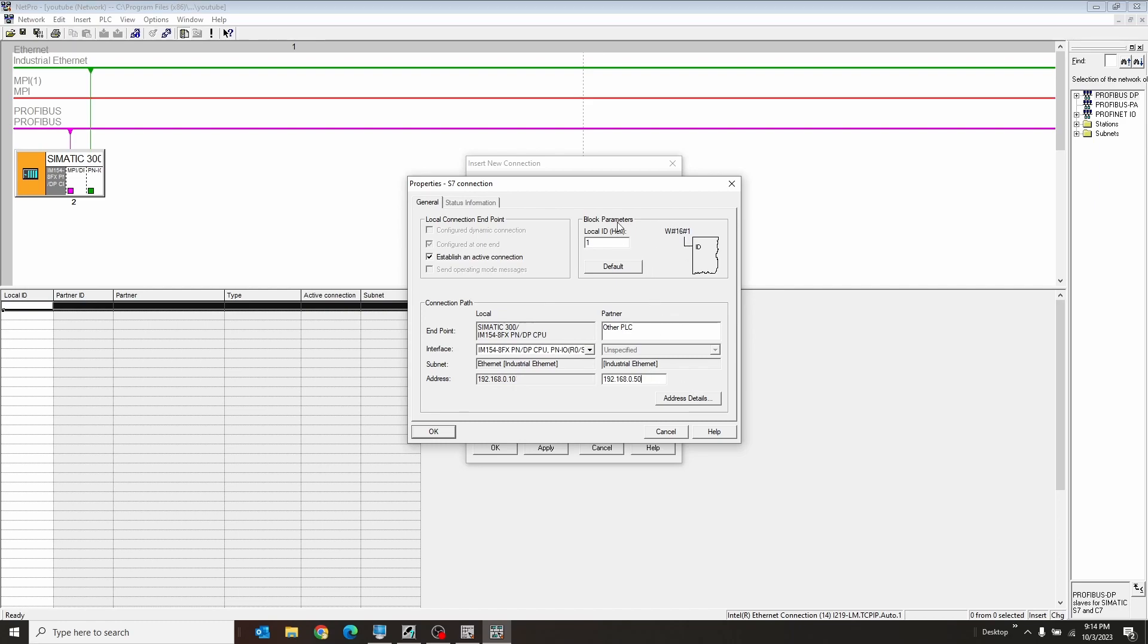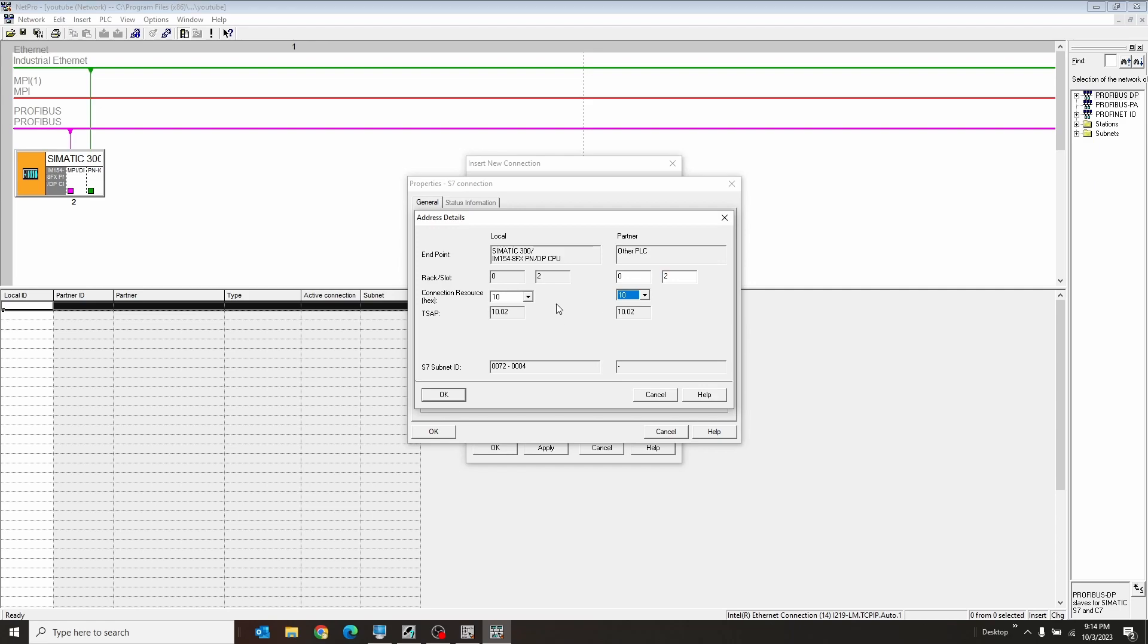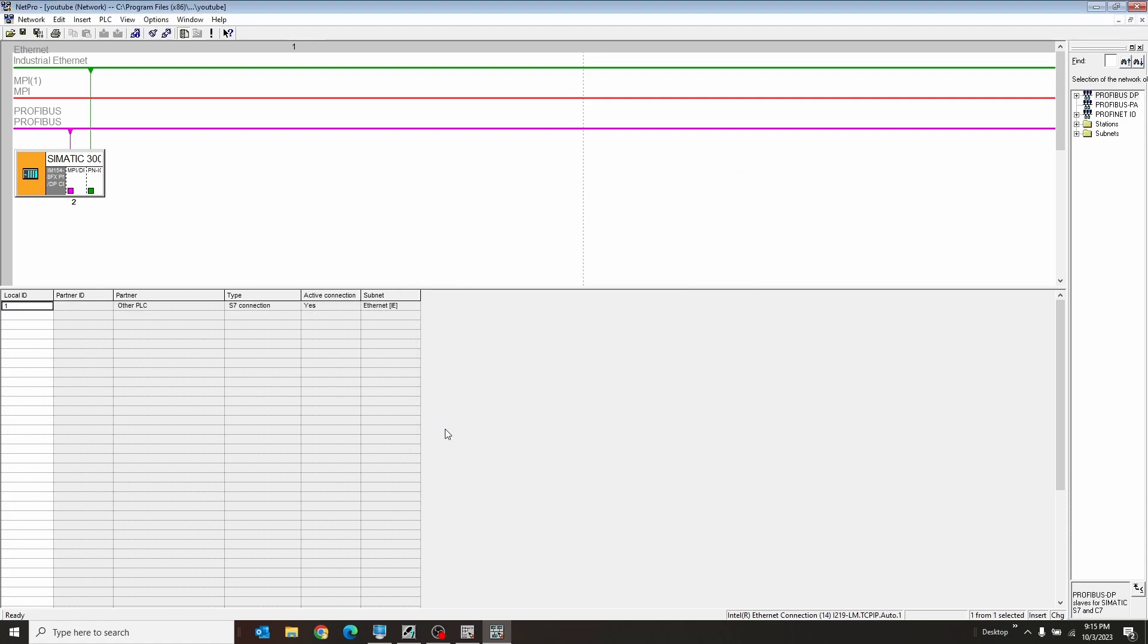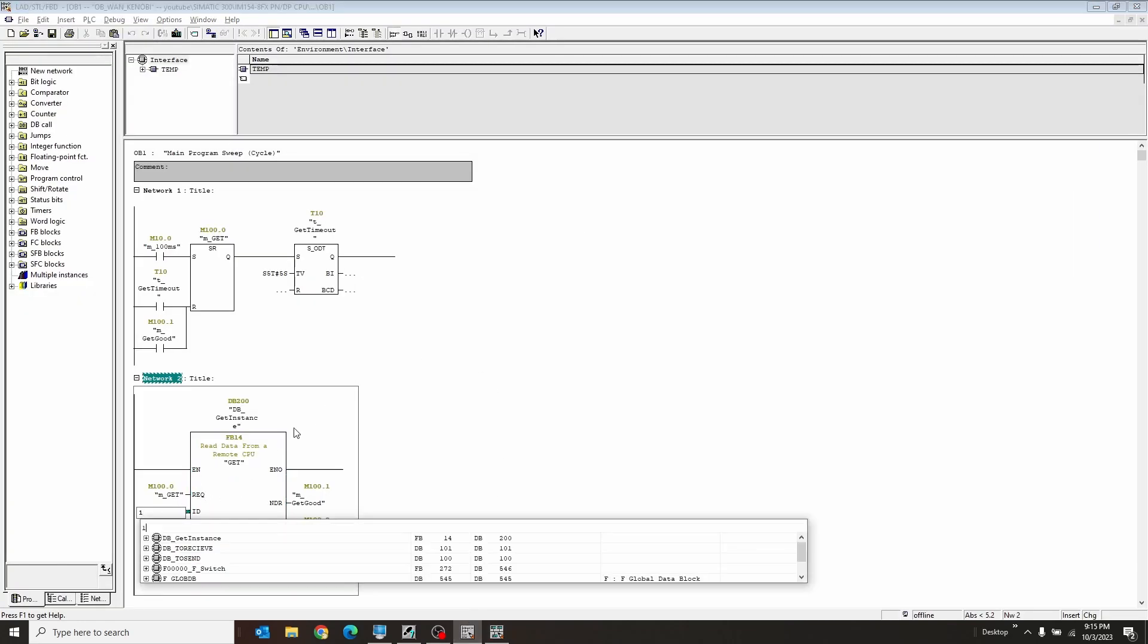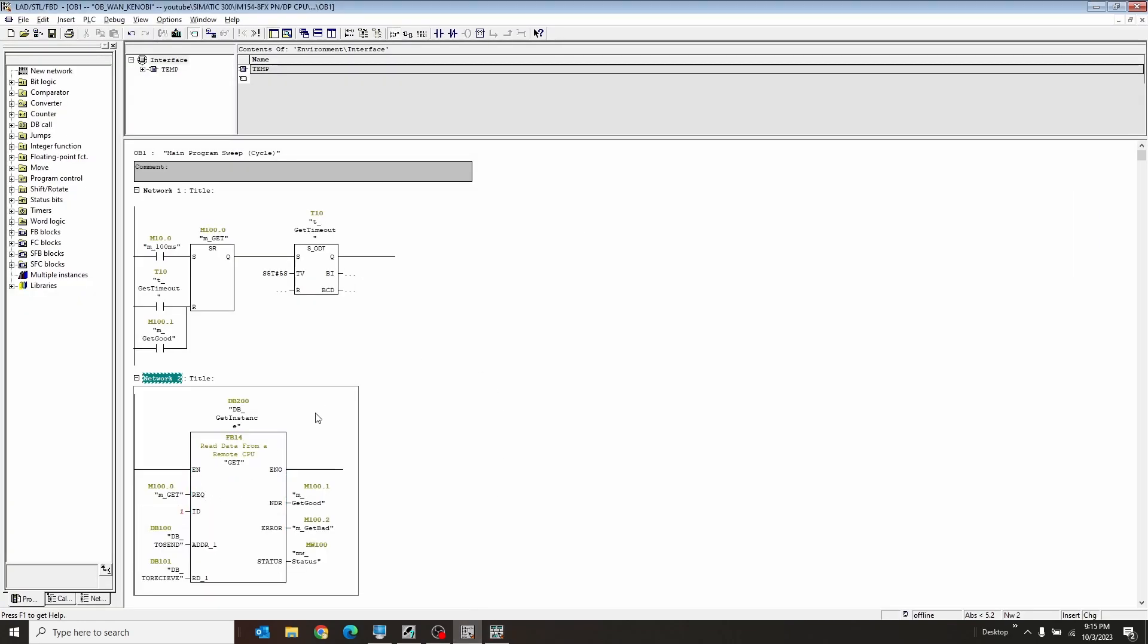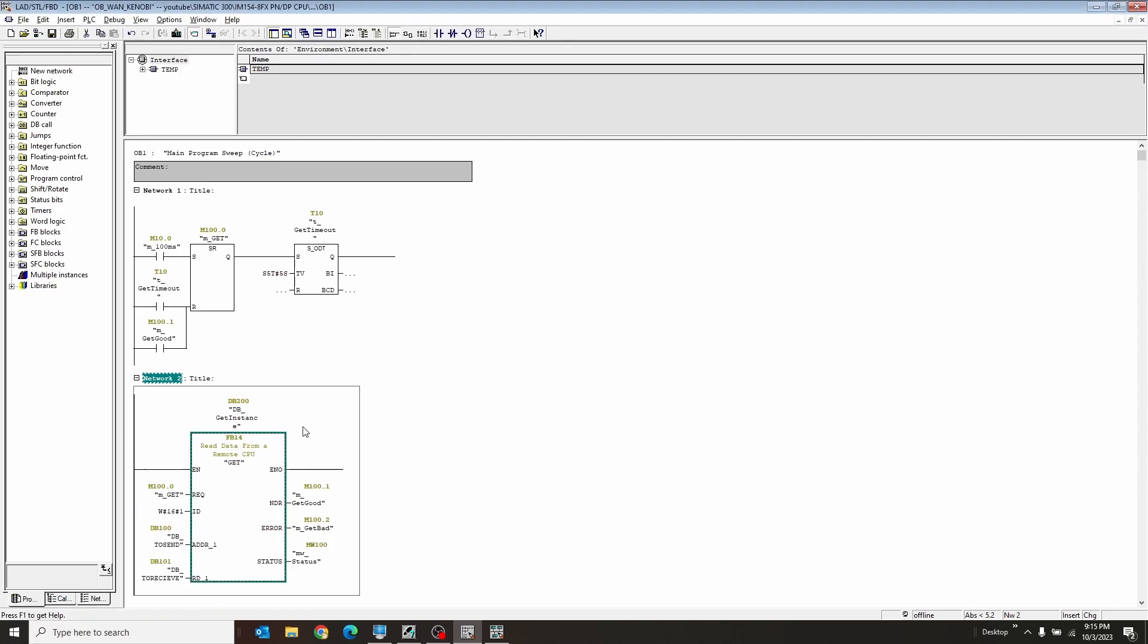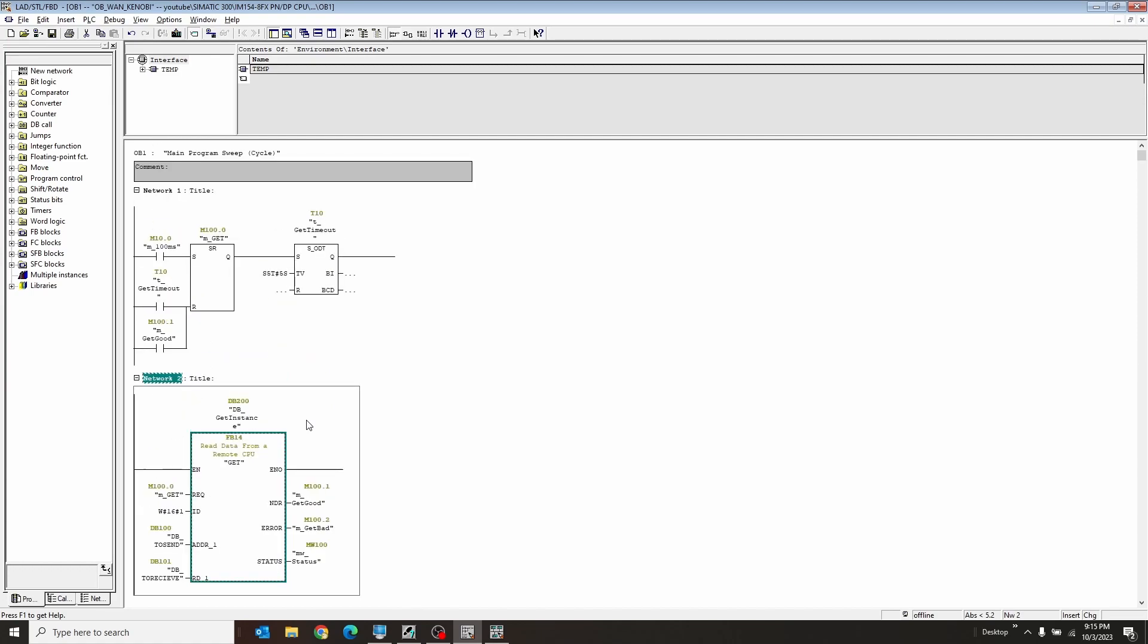This is also important. Remember this, the block parameter. I'm going to get to that back in a second. Address detail. I want the other PLC. Since our PLC is on rack 0 slot 2, the other PLC is also rack 0 slot 2. So I just changed that to 2. I'm going to change these both to be resource 10. So that matches as well. Now, this local ID here goes right here into ID. Of course, it doesn't like just that. So it's got to be like W pound 16 pound 1.